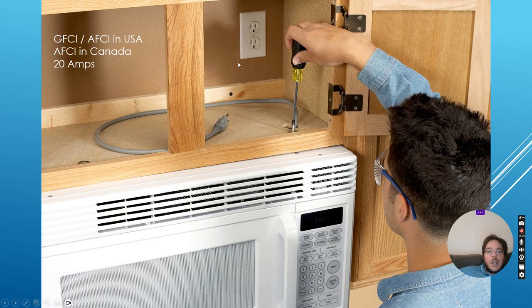Now, you also need a separate circuit and receptacle for your microwave. Again, 20 amps. It must be. Now, I'm just gonna skip this and let you know. In the United States, every single receptacle in your kitchen now, under the National Electric Code, must be GFCI and AFCI rated. In Canada, it's a little up and down. There's certain receptacles that are GFCI and certain receptacles that are AFCI. The US has gotten very strict though.